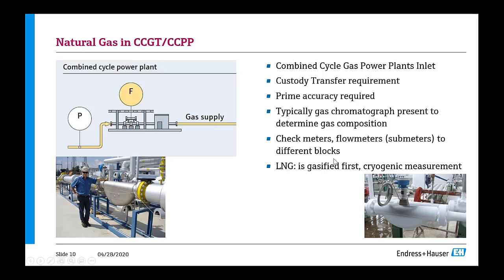Here we already see the natural gas application at the metering station. At the inlet, that's usually a custody transfer application, so in Europe, MI002 requirements. And you want to have prime accuracy because here you're talking about a lot of money. You're talking about literally millions per year that you're burning in natural gas. Typically you have a gas chromatograph because you want to know what you get supplied, so you know the quality of what is coming in.